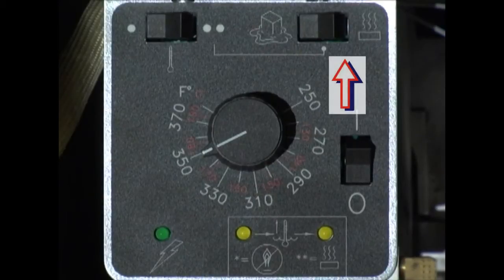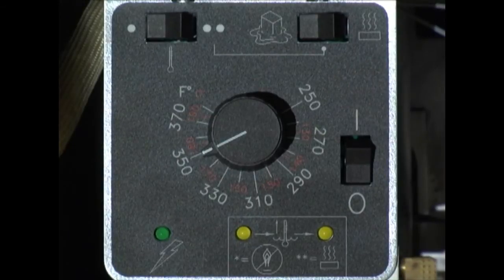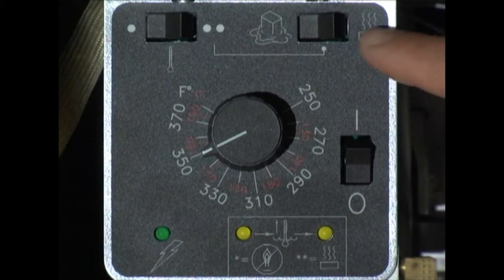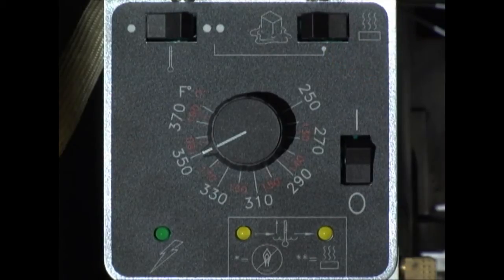In the melt cycle position, melt cycle will be executed when the appliance first starts up. This melt cycle will end automatically when the temperature conditions are correct to allow full heat. Operators may bypass a running melt cycle by moving the switch to the full heat position.